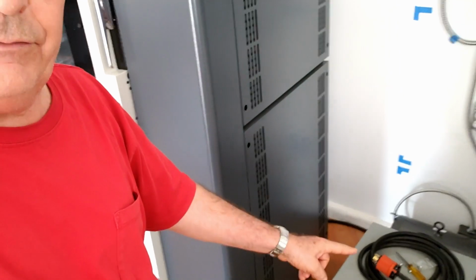So anyway, all the voltages were within range. I got anywhere from 241.5 and the max was 264. They said it would be over what is normal, 240 volts, but once there's a load on it, it'll balance out and settle down. So that's what has to go into the transformer - 240 volts - and then the transformer kicks it down to 230 for the machine. So now the next step is to plug in the machine.